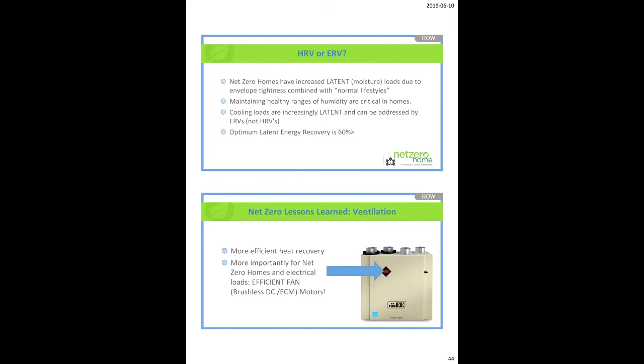No. An ERV allows you to continue to use your air conditioning because when the air is already being pre-cooled by the air conditioner, it vents the cold air out and it actually pre-dehumidifies the incoming air. I think some of the studies at the CCHT homes said it adds about 20% efficiency to the air conditioner over and above an HRV. So again, something that we're seeing.